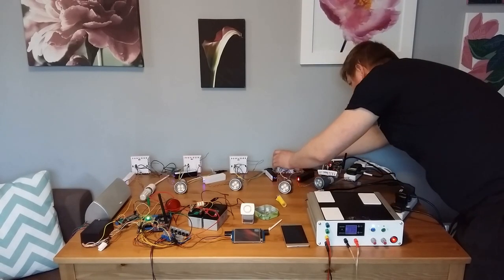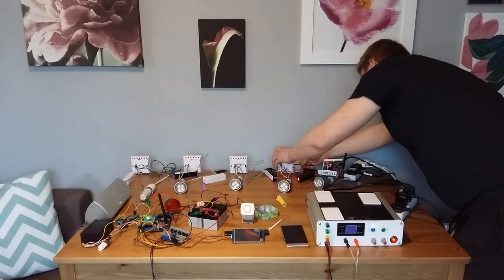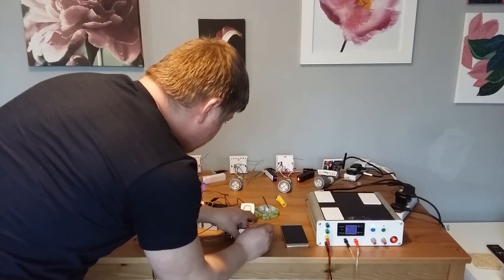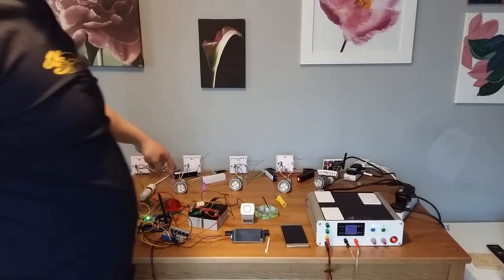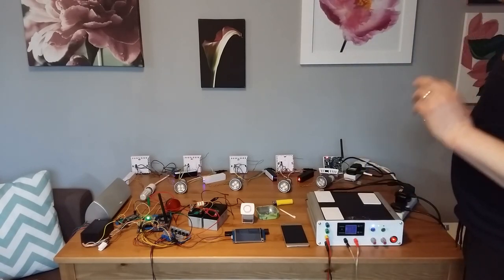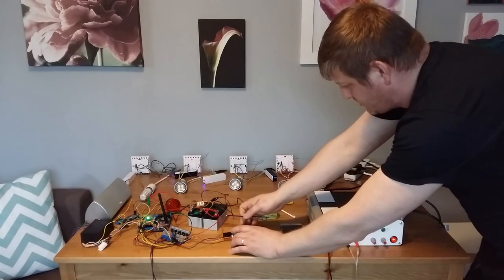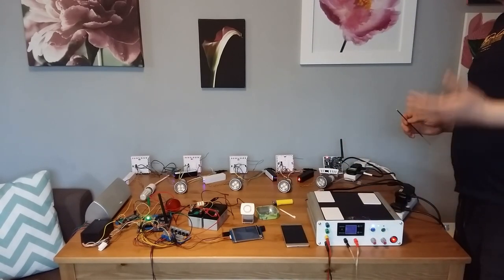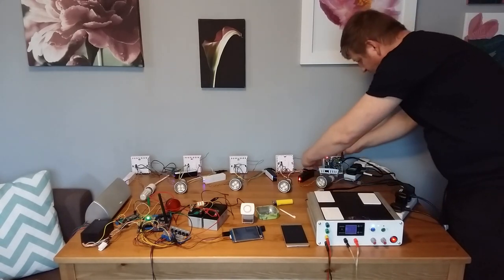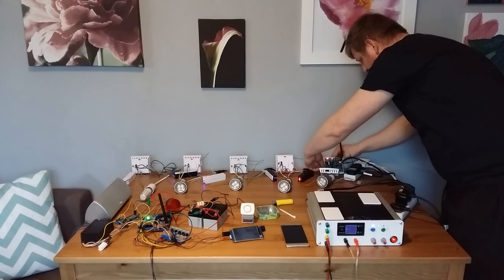So this one is the children's room. I detected smoke in the children's room. It detects smoke also here. Let me reset it. I will not let it go to the full bells anymore because I already demonstrated that one. The bathroom one will be not that sensitive, because in the bathroom when you take a shower there is a lot of steam, so I don't want to turn on the alarm because of the steam, so it will take more time until it detects the smoke. So let's stay longer there.